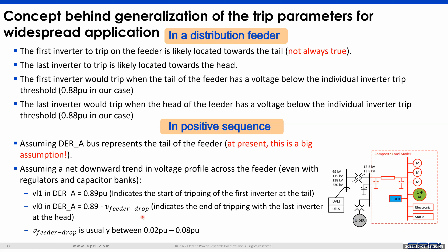Now we can translate that to a positive sequence by assuming the bus where the DERA is located is the tail end of the feeder. It's still a big assumption, but so far it has helped our analysis. If we assume the net downward trend of voltage, we can use heuristics or rules of thumb, especially regarding how much the voltage drops across the feeder, to set up the parameter values of the DERA model and generate the tripping profile we want to see.